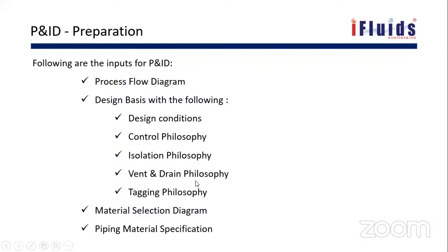So before opening any flange, any vessel or any equipment, you need to depressurize the system, whatever you are going to open. So before opening anything for your maintenance work, it will be vented and drained to ensure there is no pressure inside. So those things will be captured from the philosophy. What is the vent and drain philosophy?